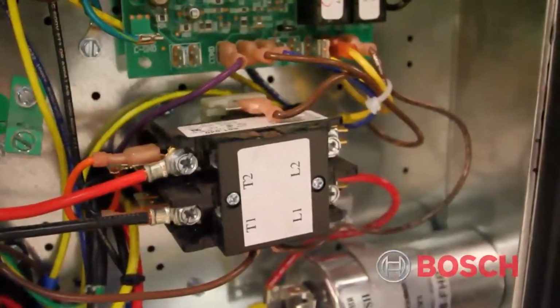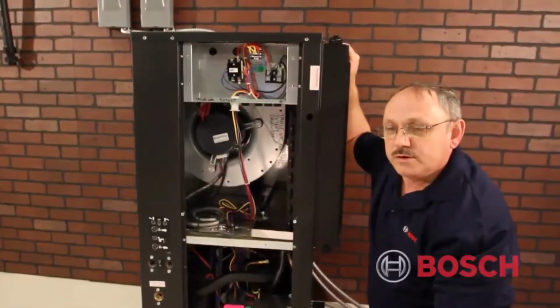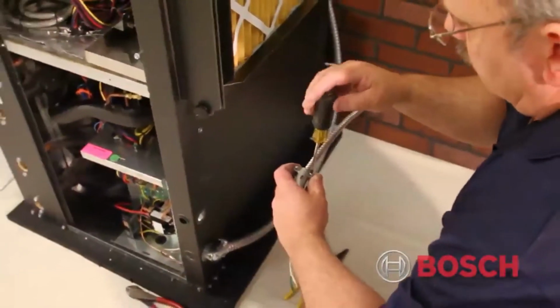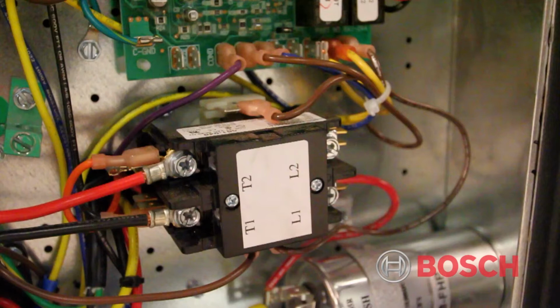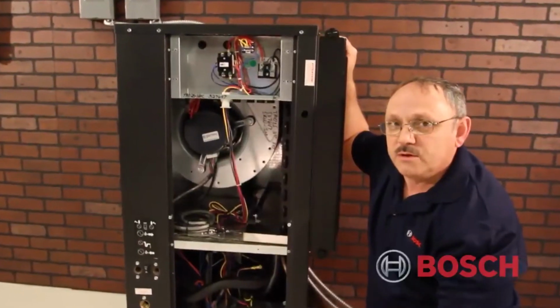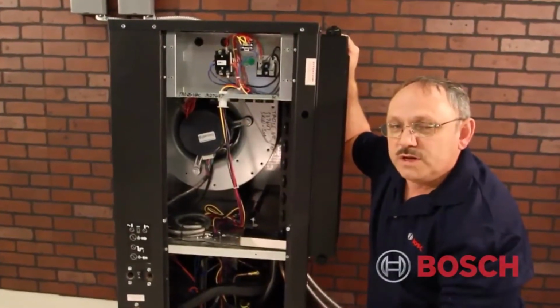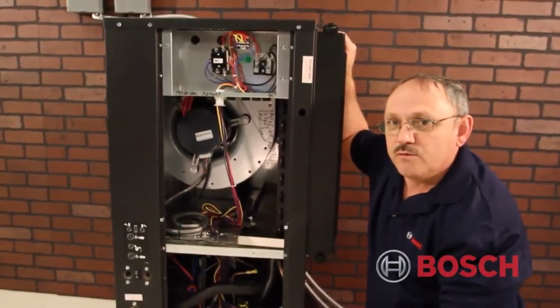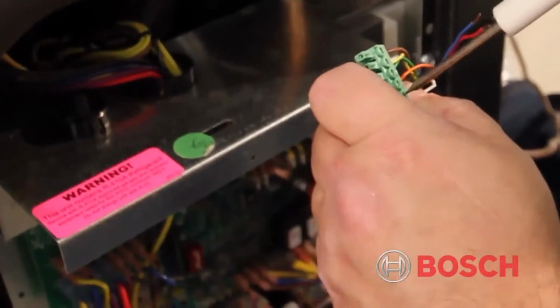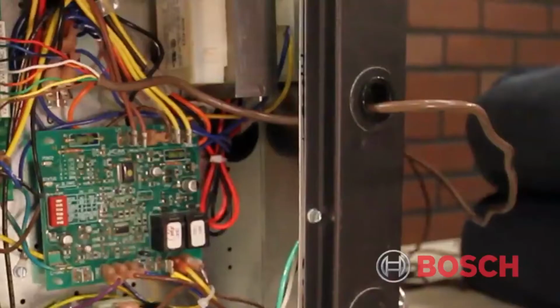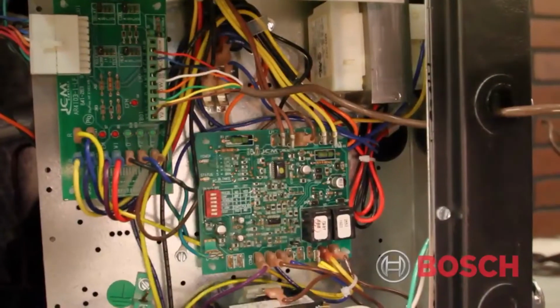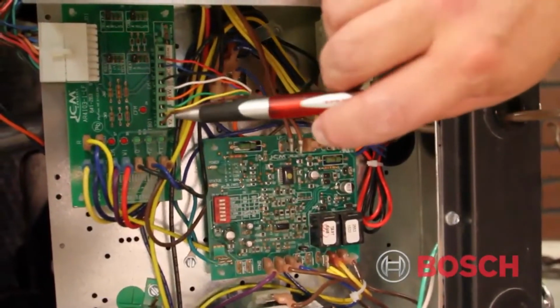We'll also at this time run our power supply for our circulating pumps, and we will wire those connections up to T1 and T2 of the contactor. This will allow the circulating pumps to operate anytime that the equipment is operating. Once we get those connections made, we will make our low voltage connections. There's also a concentric adapter in the front with the grommet already installed. We'll make those low voltage connections at a terminal board that is located on the ECM motor control board.